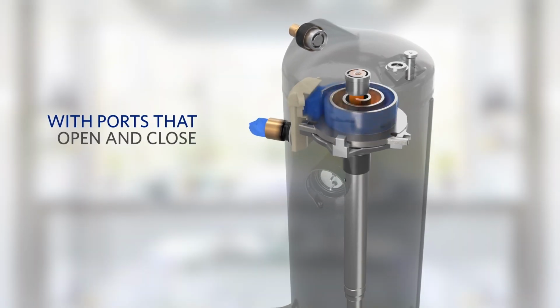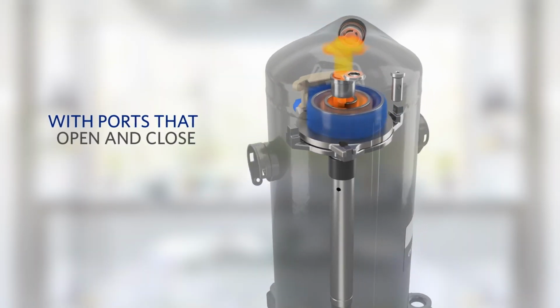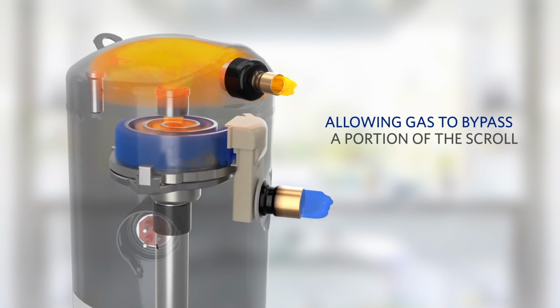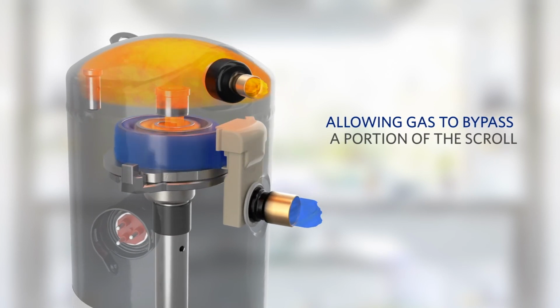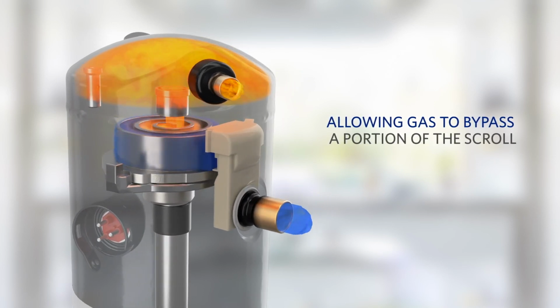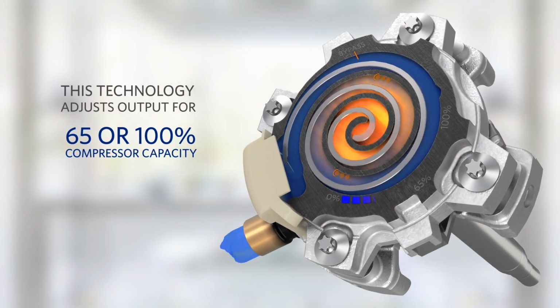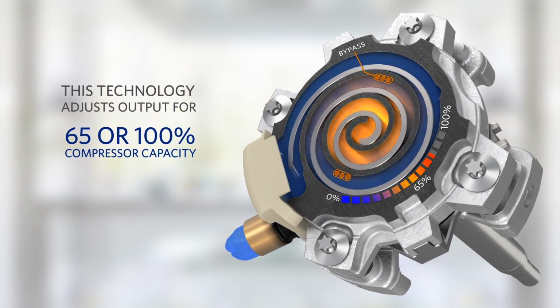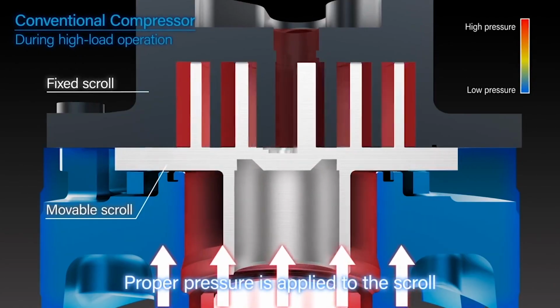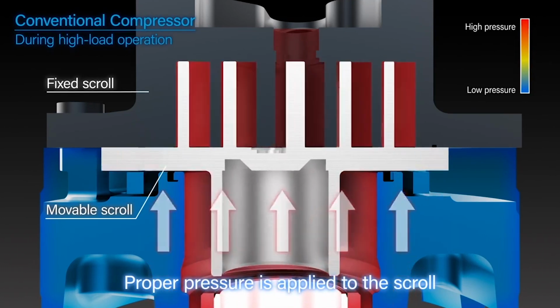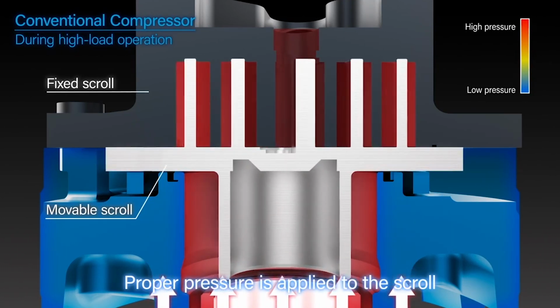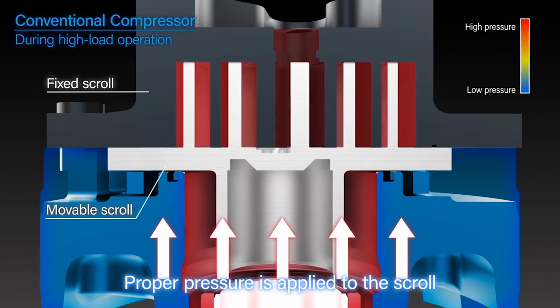Digital scroll compressors use the concept of hot gas bypass and integrate it into the compressor. The compressor can separate the scrolls within the compressor, allowing the refrigerant to bypass the compression cycle, thus reducing the compressor output at a low speed. Digital scroll compressors use electronics within the compressor to reduce the output while running at a fixed speed of 100%. Like hot gas bypass, digital scrolls offer part load operation and load matching, but at reduced efficiency.